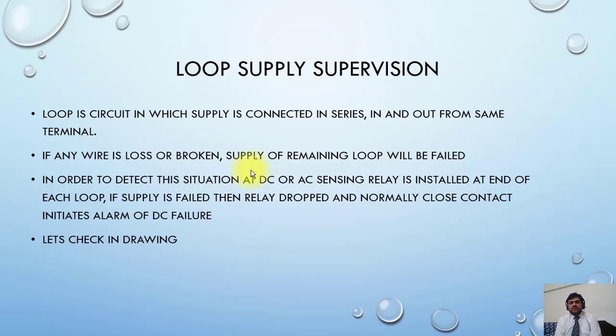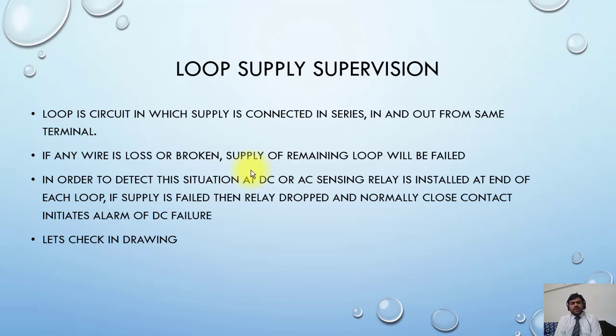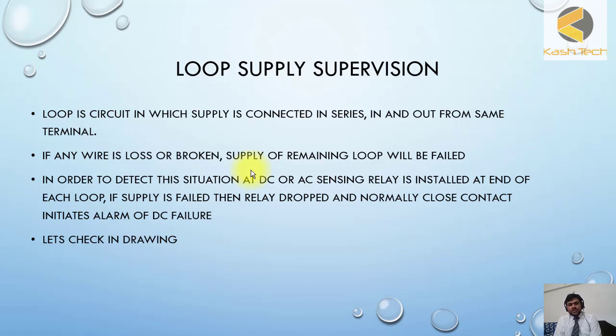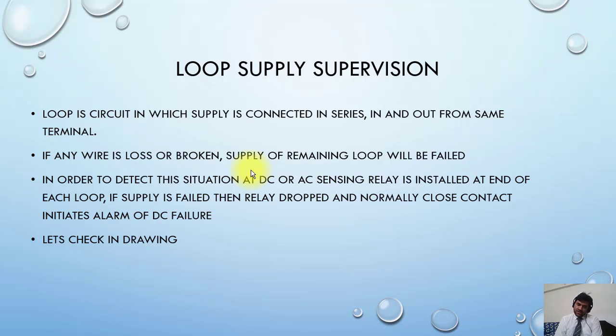If any wire is loose or broken, supply of the remaining loop will fail or be disconnected. In order to detect this situation, a DC or AC sensing relay is installed at the end of each loop. If supply fails, the relay drops and the normally closed contact initiates an alarm of DC failure.